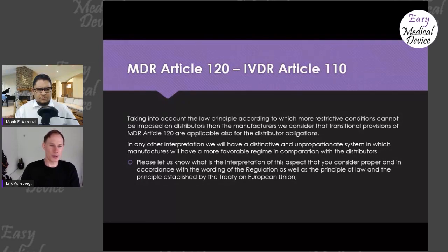On the other hand, there are also companies that say no, that's not how you should actually read Article 120 Section 3, because it explicitly says it is intended to create an exception to Article 5, which is the core article of the MDR stating that every device placed on the market has to be in conformity with this regulation. Now you get into this whole spiraling circular reasoning thing.